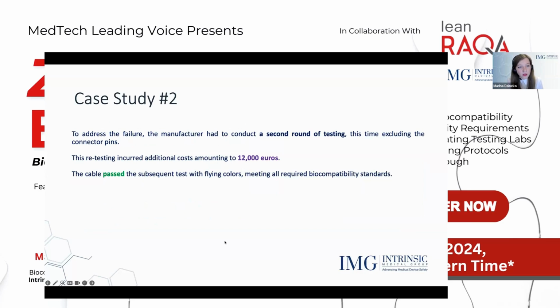And here you may see, unfortunately, the manufacturer lost around 12,000 euros because they were forced to repeat this test, just removing these connector pins. And yeah, the test passed and all good here. So that's why the biological evaluation shall contain the information not only on the medical device, the whole picture and intended use, but also we need to break down what components are here, and what the contact type with the patient is for each component.